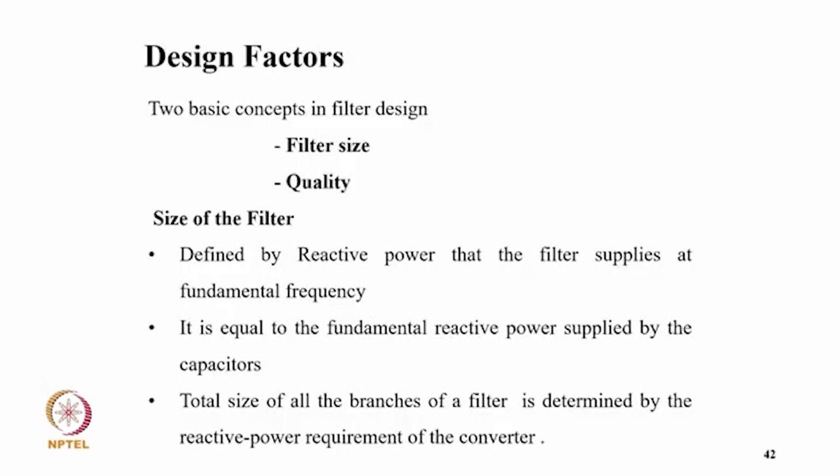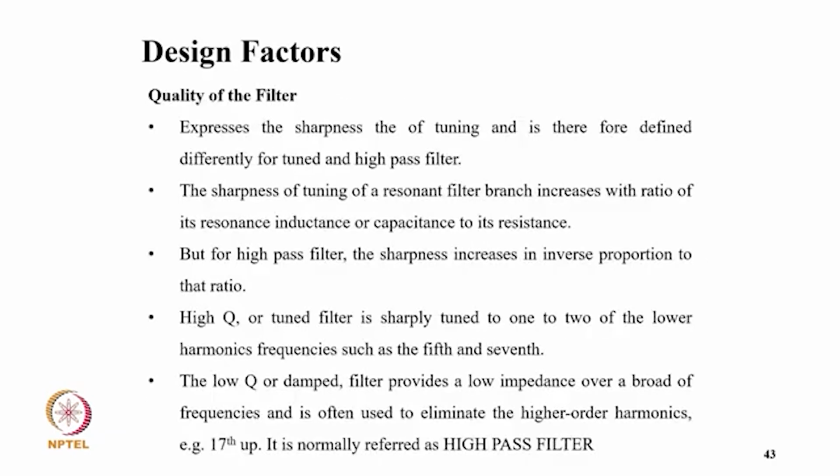So now typically design factors, two basic concepts in the filter design: filter size and quality. And the size of the filter is defined by the reactive power that the filter supplies at fundamental frequency, and it is equal to the fundamental reactive power supplied by the capacitor, and the total size of all branches of the filter is determined by the reactive power requirement of the converter.